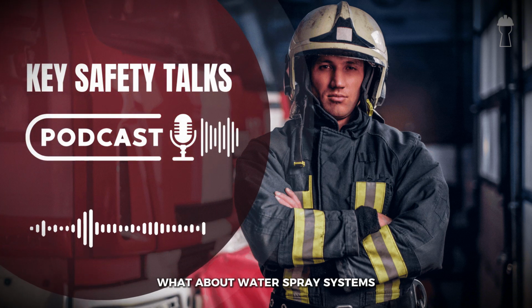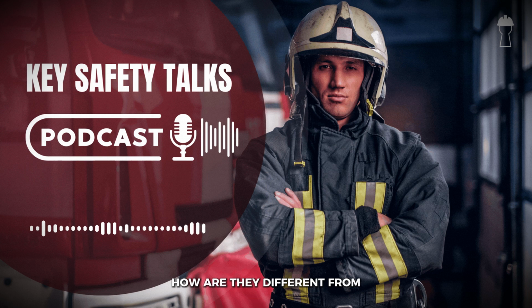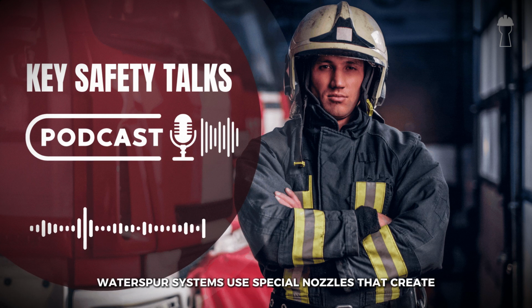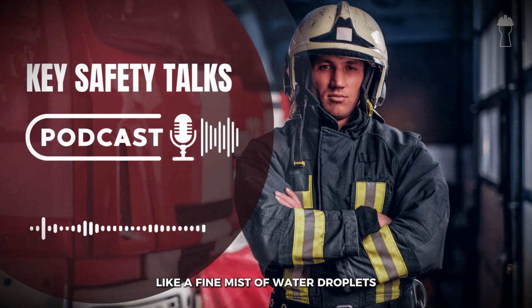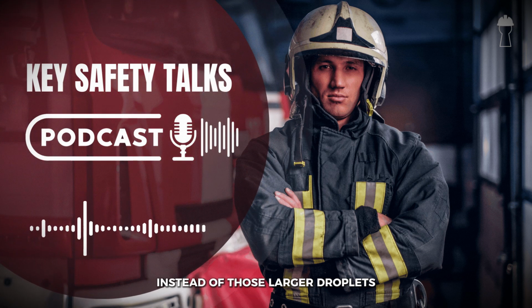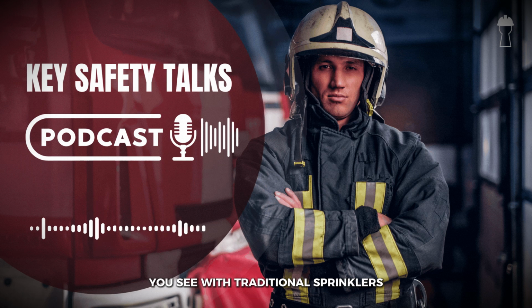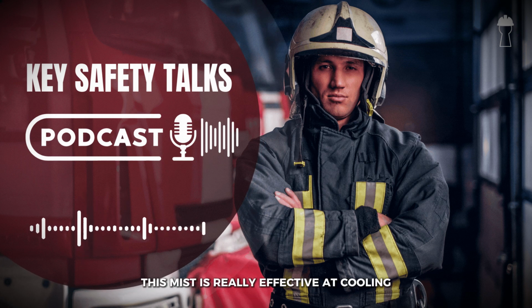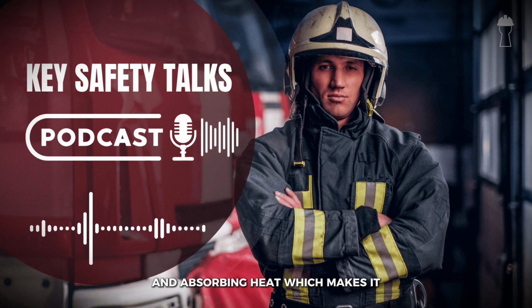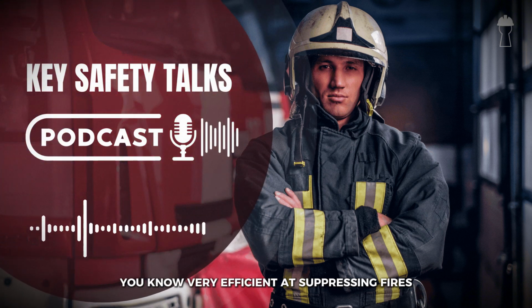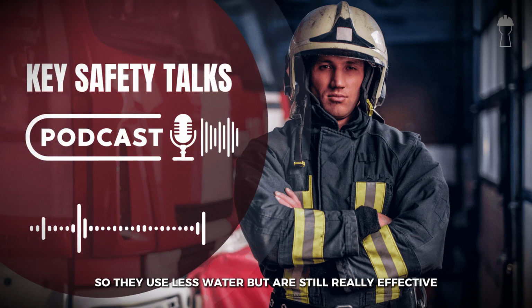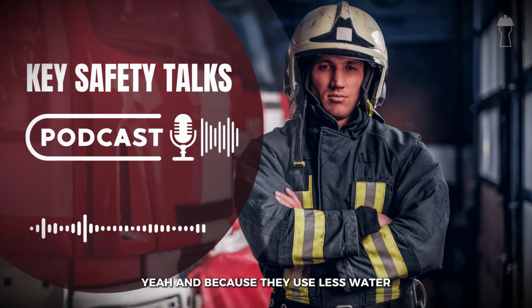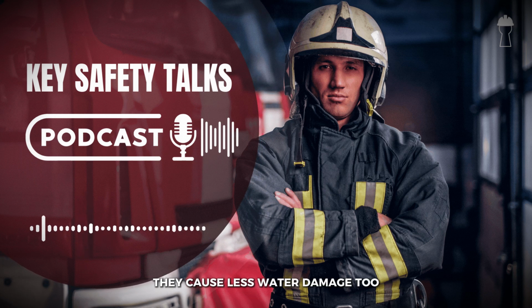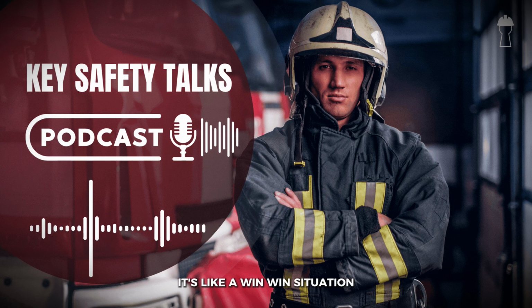What about water spray systems? How are they different from your typical sprinkler system? Water spray systems use special nozzles that create a fine mist of water droplets instead of those larger droplets you see with traditional sprinklers. This mist is really effective at cooling and absorbing heat, which makes it very efficient at suppressing fires. So they use less water but are still really effective. Yeah, and because they use less water, they cause less water damage too. It's like a win-win situation.